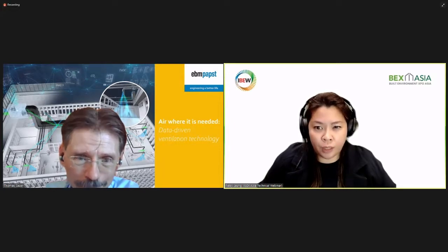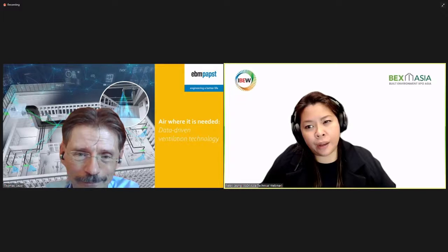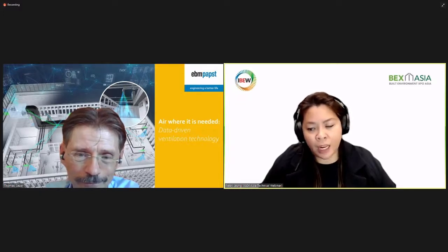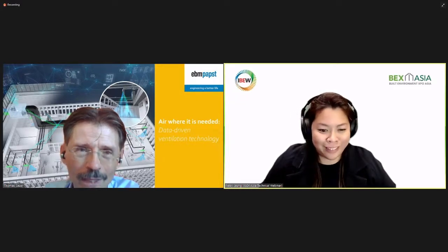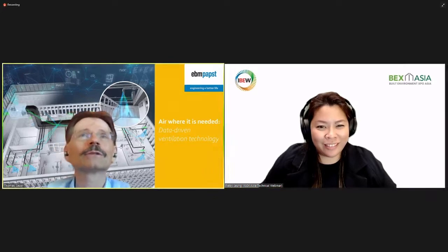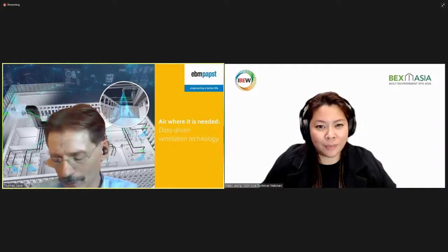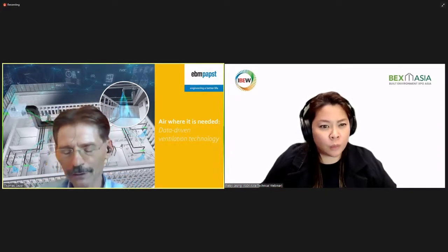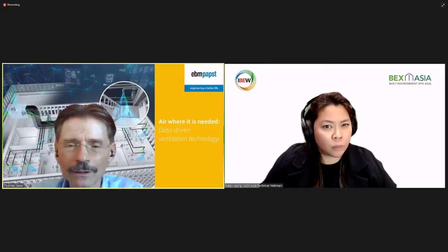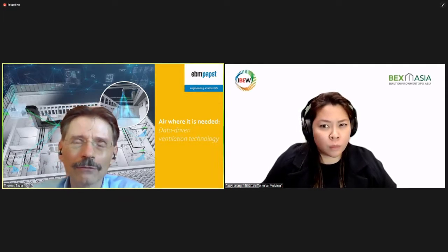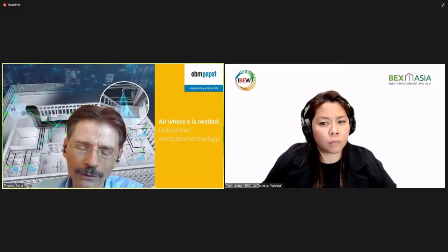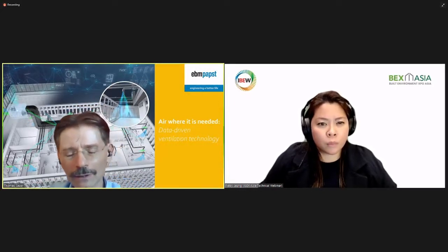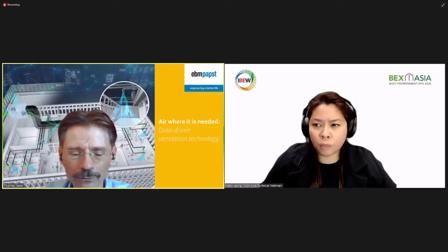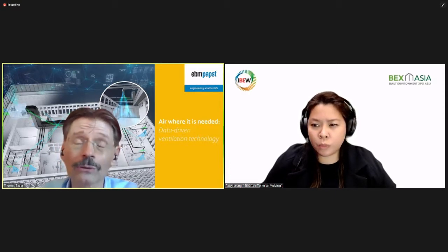Thank you for that. And how is the whole air side system balanced within the AHU system, Thomas? There is several balancing going on. The first, let's say the nucleus, is inside we have the fans that deliver air into a room and the fans that exhaust the air out of a room. These are balanced to each other so that the airflow matches, so that we again have zero pressure in the room.